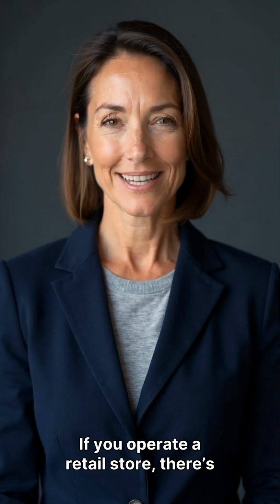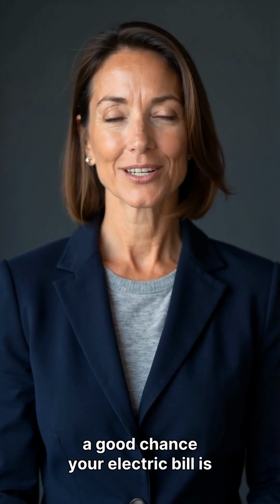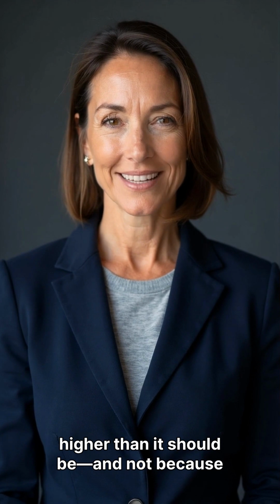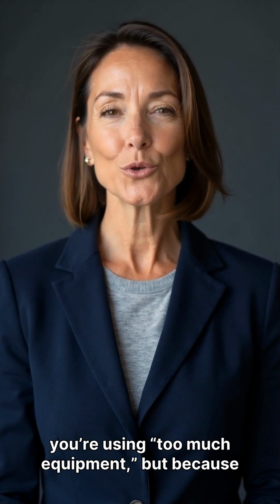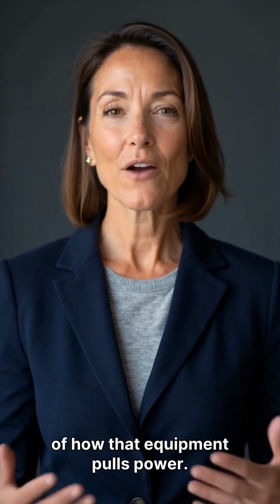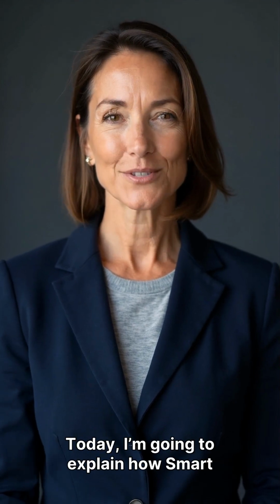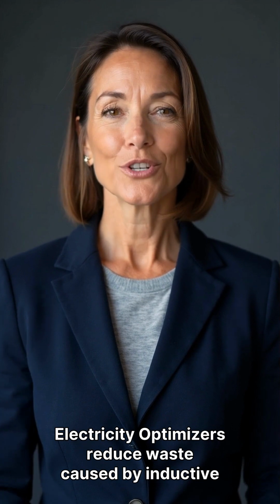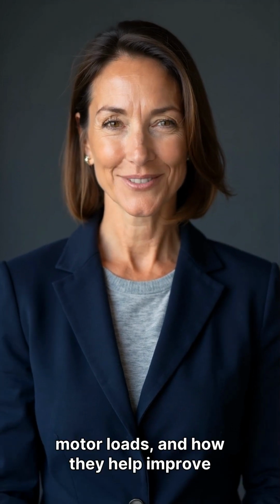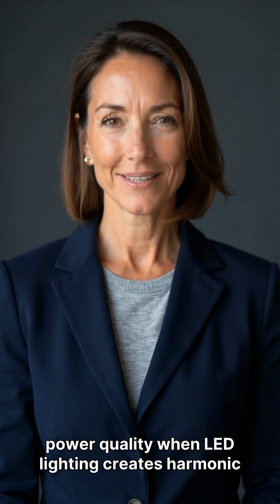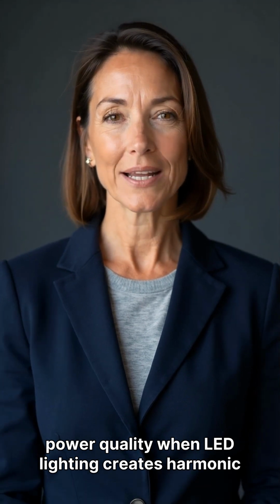If you operate a retail store, there's a good chance your electric bill is higher than it should be. And not because you're using too much equipment, but because of how that equipment pulls power. Today, I'm going to explain how smart electricity optimizers reduce waste caused by inductive motor loads, and how they help improve power quality when LED lighting creates harmonic distortion.